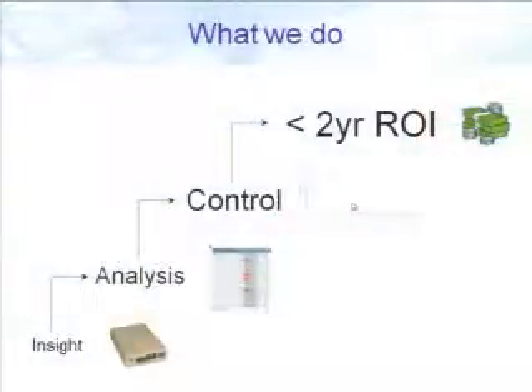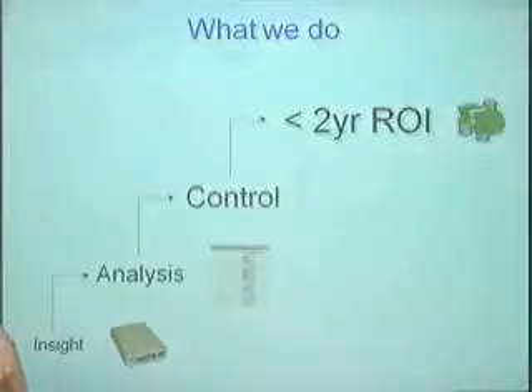It actually has outputs, so we can plug directly into variable frequency drives on the control or cooling units, or chilled water valves, or both, to directly control the units. Many of our customers have pretty basic data centers with standalone cooling units, so we can directly control them—doing both sensing and control wirelessly.